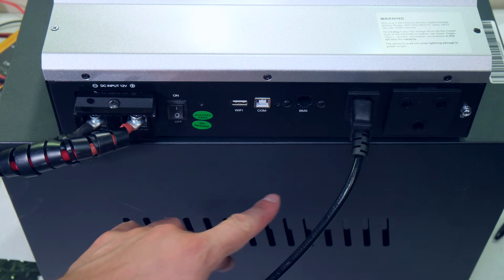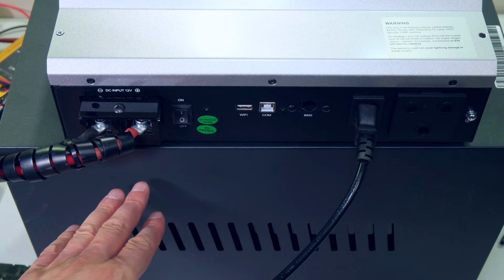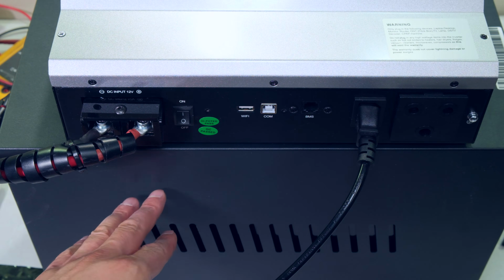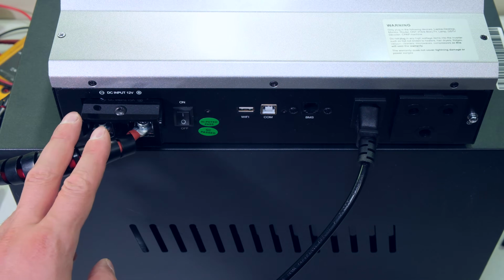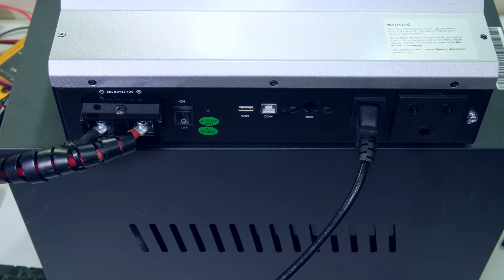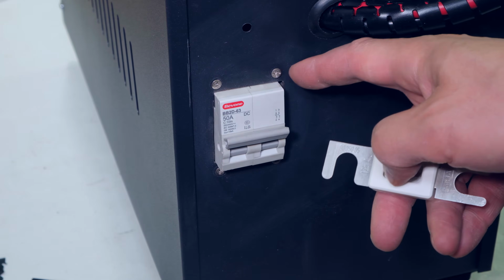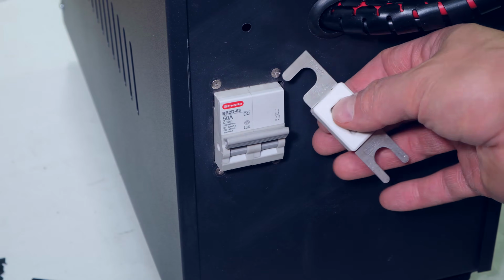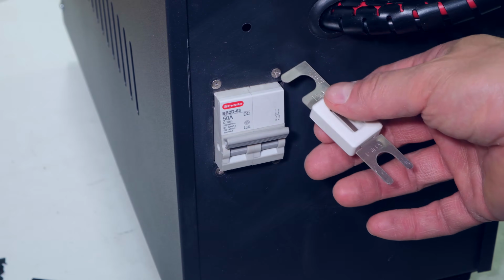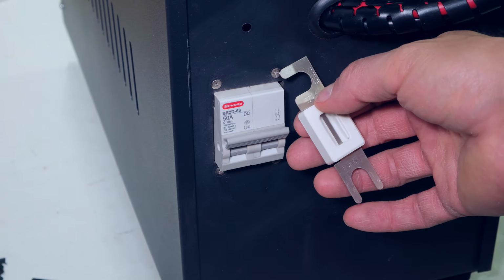Right, just a tip, the wire from the battery to the circuit breaker should be as short as possible, and then from the circuit breaker to the inverter should also be as short as possible. That will reduce any unnecessary volt drop. Right, there's the circuit breaker, which is now protecting the battery, and I also showed how to use a fuse if you also want to do a fuse protected battery.